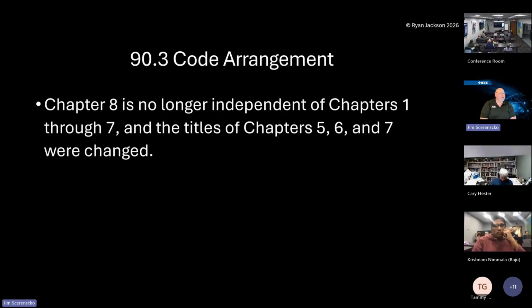The code arrangement has been changing quite a bit over the last couple cycles. The big change this time is Chapter 8 is no longer independent. I don't know if you noticed or not, but Chapter 8 was never part of the NEC. It was an independent book. All that communication stuff was independent. And the only time you had to do anything that was listed as far as grounding and bonding or supporting or anything like that was if it was specifically called out in Chapter 8.